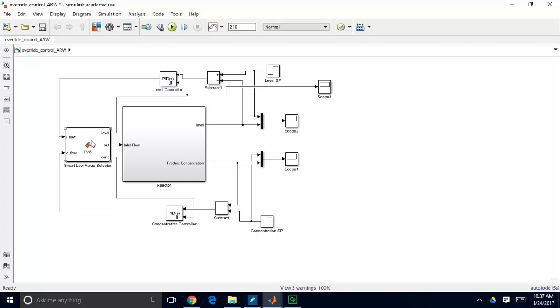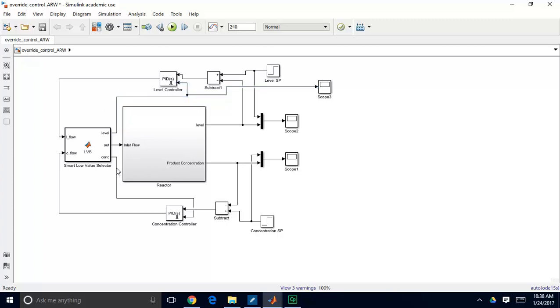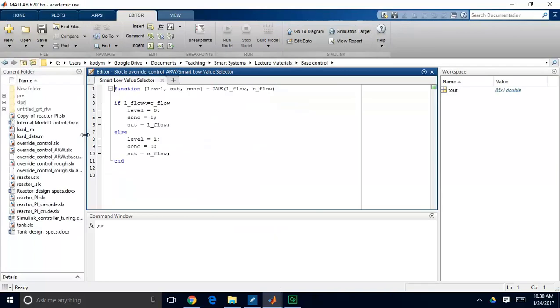The external information that this is giving us, and I've built this into the logic myself, is when the level controller is not in control, I want this level variable to send a non-zero signal back to my PID loop. So when the level controller is not in control, I'm going to stop my PI controller from integrating by sending it a non-zero signal. And the same thing for the concentration controller. When my concentration controller is not in control, I'm going to send it this external signal that's going to stop this from integrating, which will have this anti-wind-up method built into it.